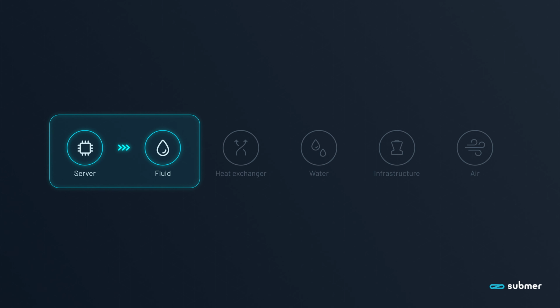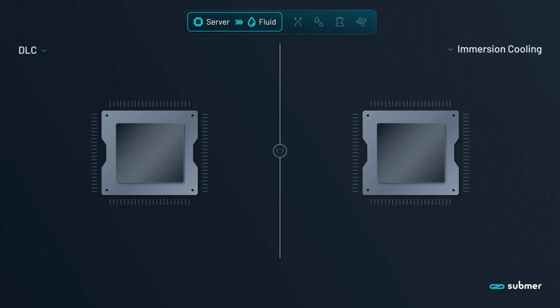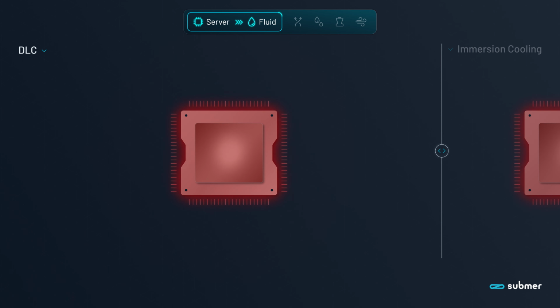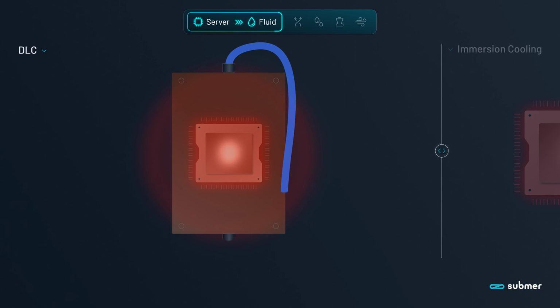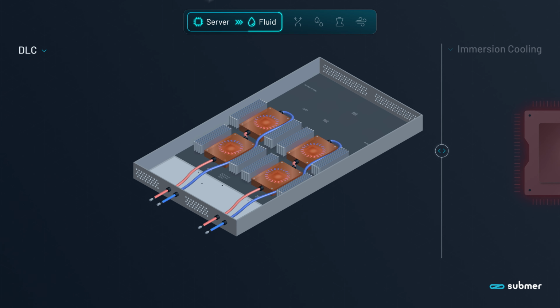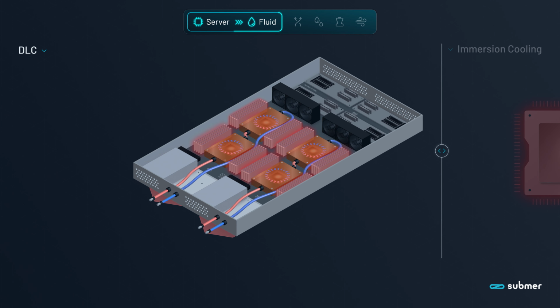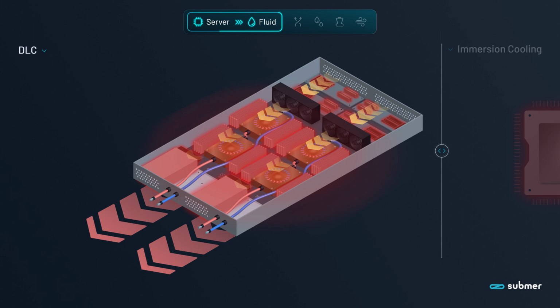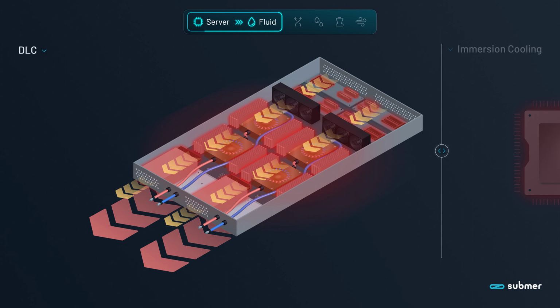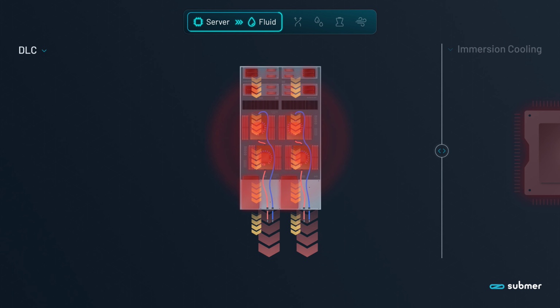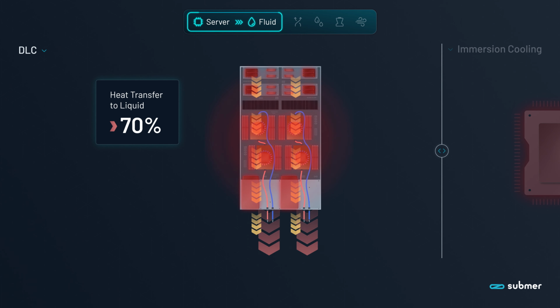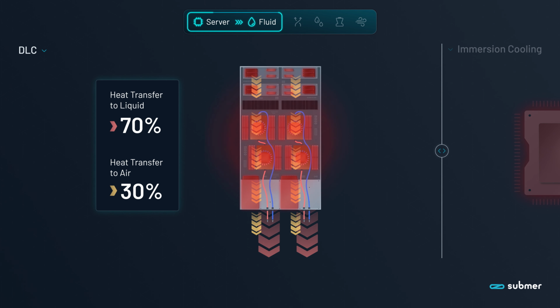The first stage is transferring heat from the server to the cooling fluid. As your IT hardware powers up, the chip, typically a CPU or a GPU, is the primary heat source. With direct liquid cooling, a cold plate is typically attached to the primary heat source, the chip. However, components like memory modules still generate heat and depend entirely on air cooling. Adding more chips means more cold plates and tubing are needed too, increasing complexity as the server equips more of them. In this scenario, only 70% of the heat is transferred to the liquid. The remaining 30% must be handled by server fans, which extract heat using air.